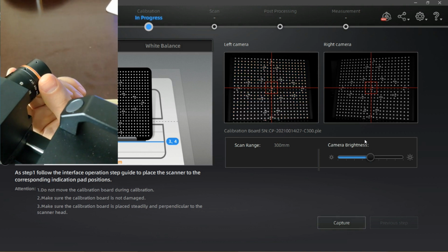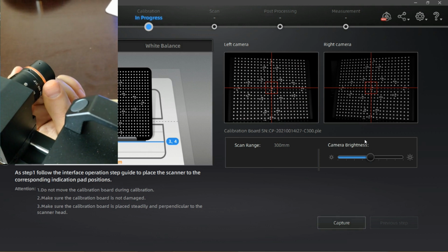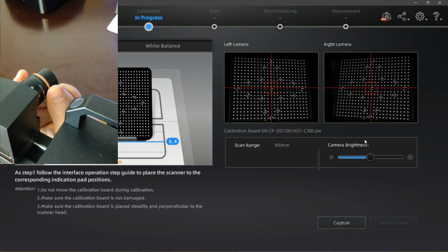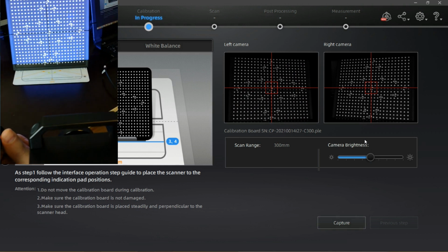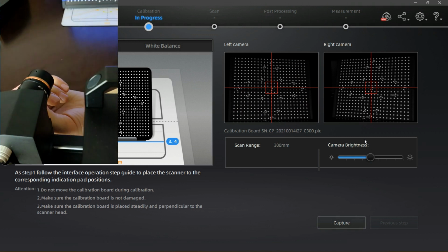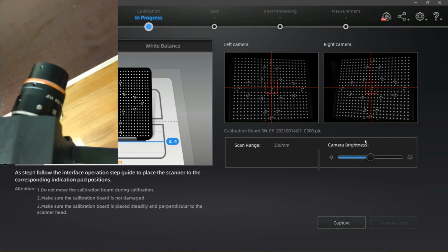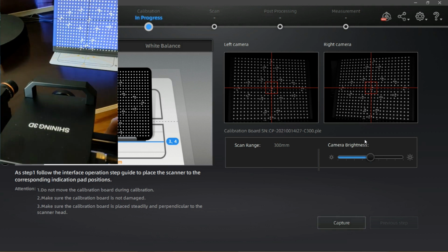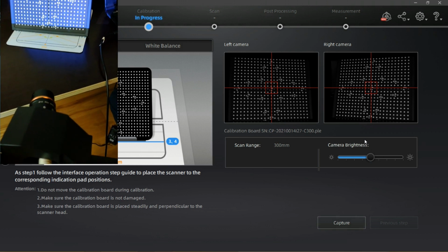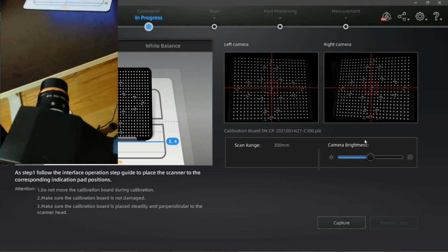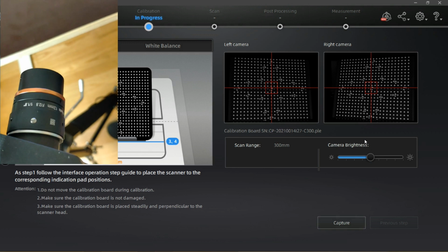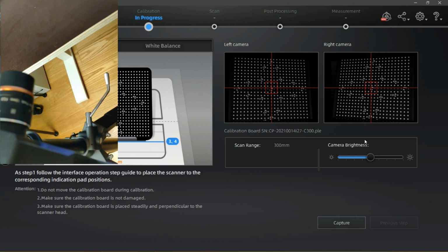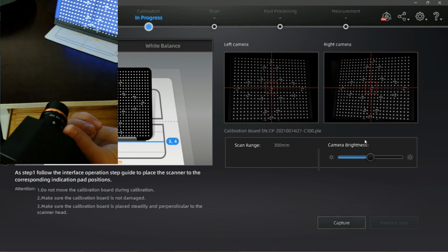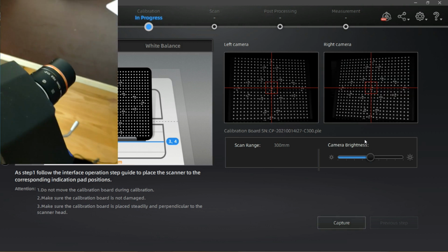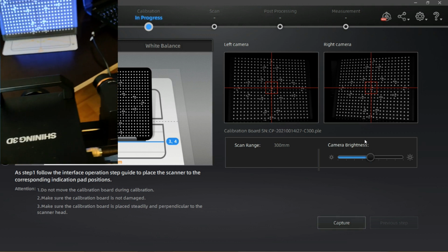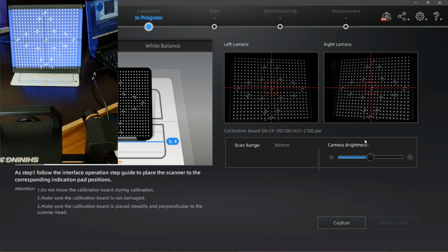Because of the slow speed of image actualization, just turn in small steps, wait, turn, wait, and that should be fine. Don't forget in the end to tighten the screws that fix your aperture, because if you later on after calibration change the aperture, your calibration is done. You will have to make a new one. You will have changed your optical setup and you will not be able to use it. So these two are done, and what rests right now is to adjust the camera sharpness.